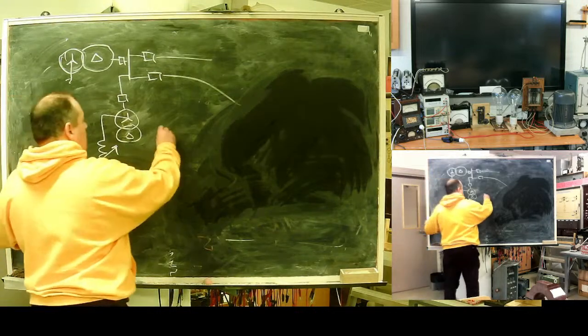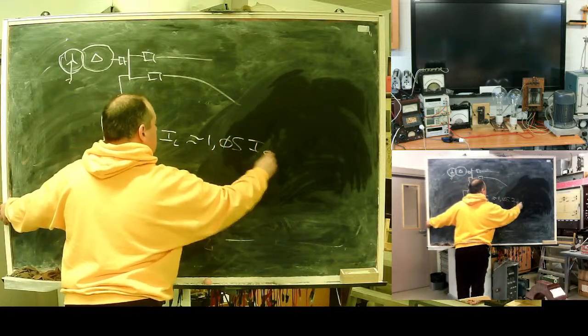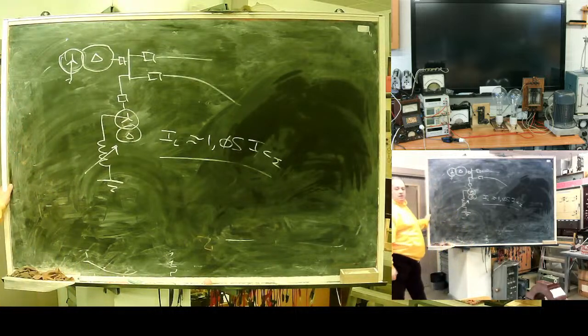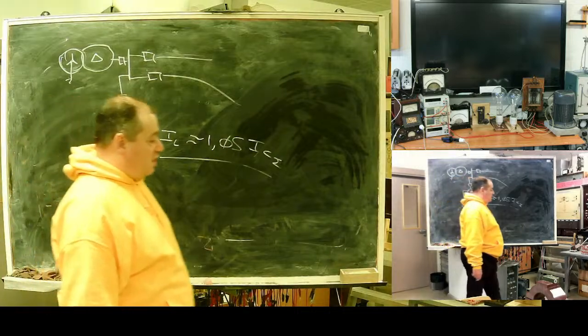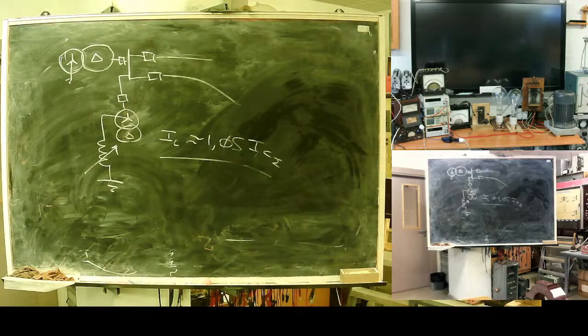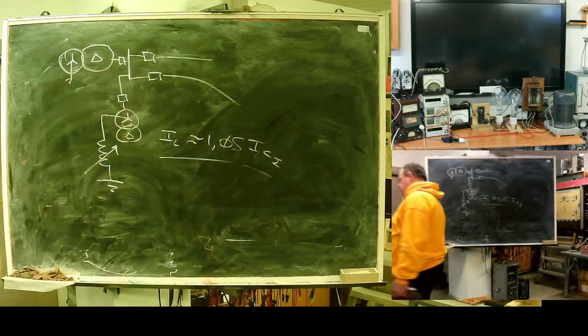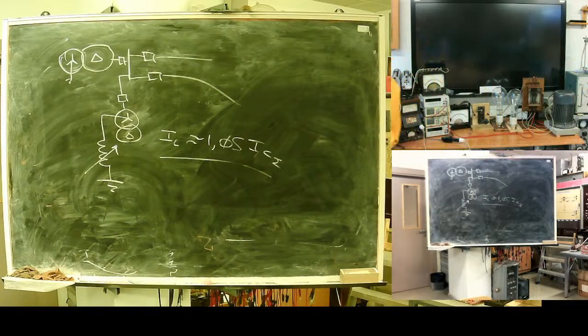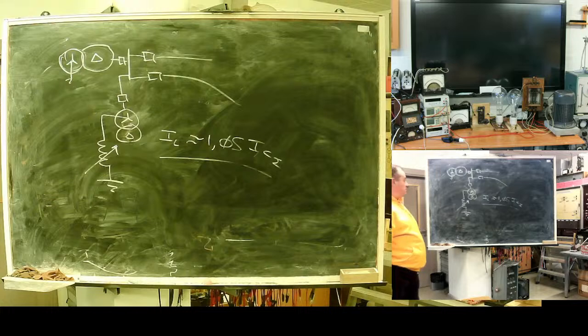This is how compensated neutral, or Peterson neutral, is created. Usually, to prevent overvoltage, IL is approximately 105 percent. Special automatic adjusters are available on the market. But there is one problem. In such a network, it is virtually impossible to detect fault direction. In an isolated neutral network, capacitive current will give you direction. In a compensated neutral, directed fault protection in its simple form will not operate. You will have no current, or you can react to coil current and give the wrong direction.